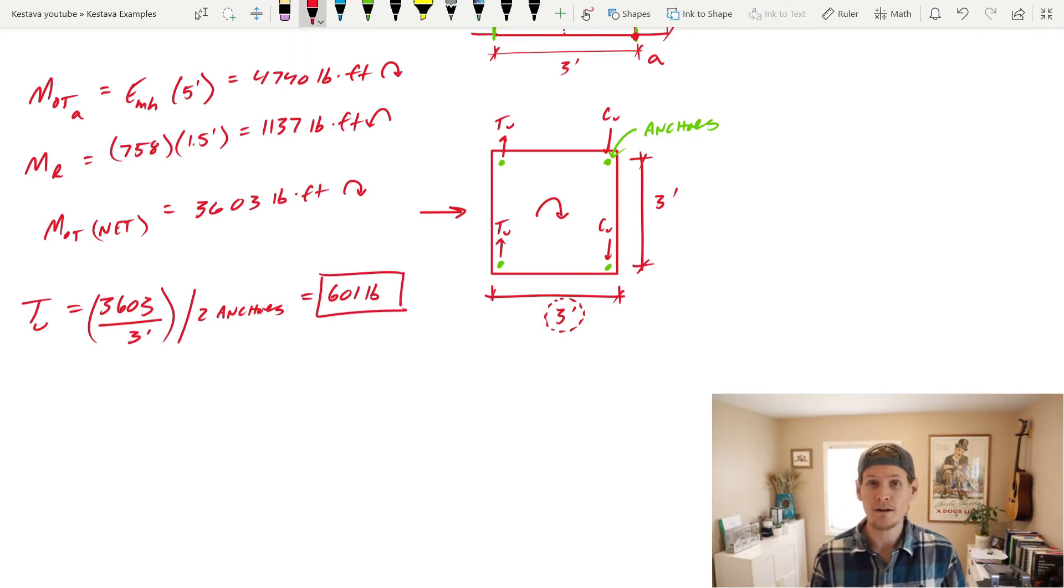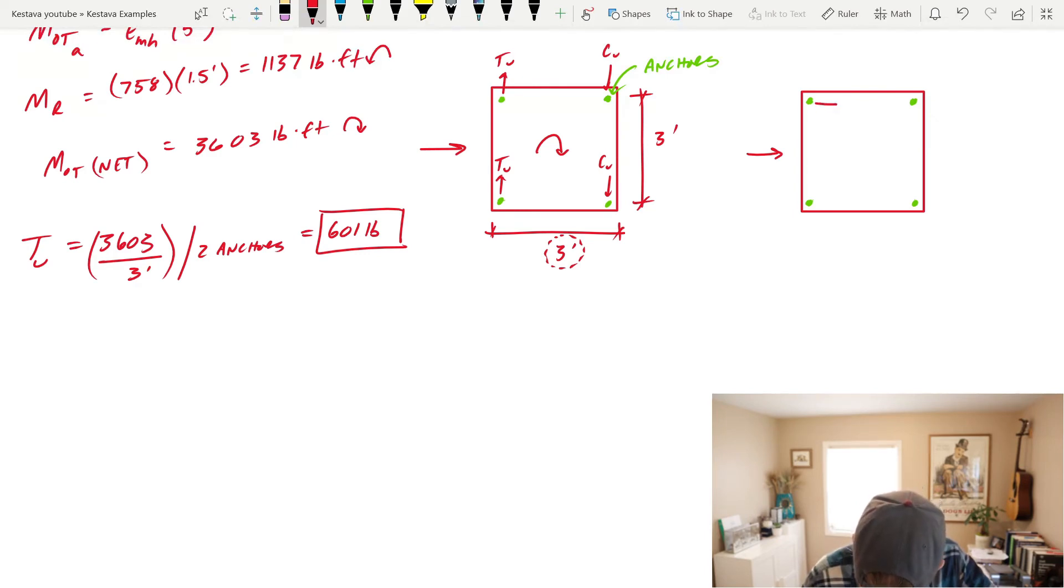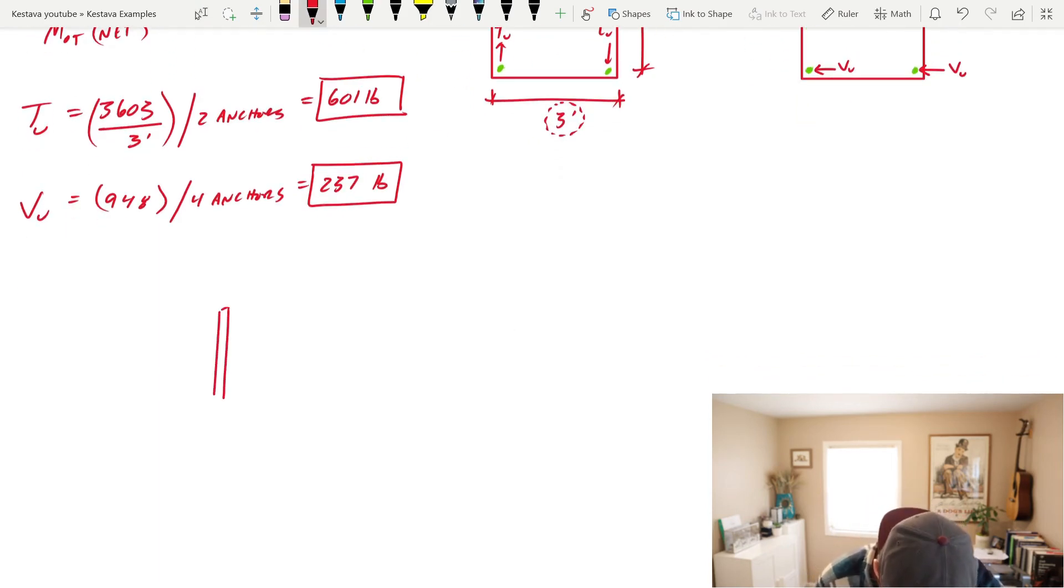And we also need to account for shear that's going to be resisted by those anchors as well. And again, you have your force moving left to right. And in this instance, all four anchors are going to resist shear evenly. So VU is just equal to your total horizontal seismic force, which we know is 948 pounds, and it's just divided by four anchors resisting that demand, which gets us 237 pounds per anchor.